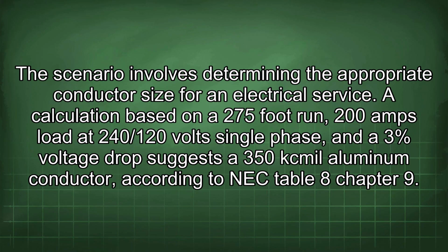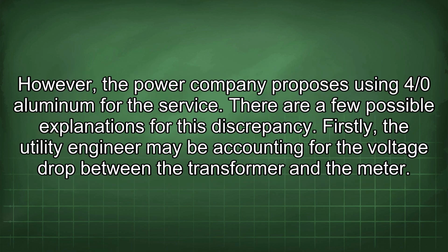The scenario involves determining the appropriate conductor size for an electrical service. A calculation based on a 275-foot run, 200 amps load at 240/120 volt single phase and a 3% voltage drop suggests a 350 kcmil aluminum conductor, according to NEC Table 8, Chapter 9. However, the power company proposes using 4/0 aluminum for the service.